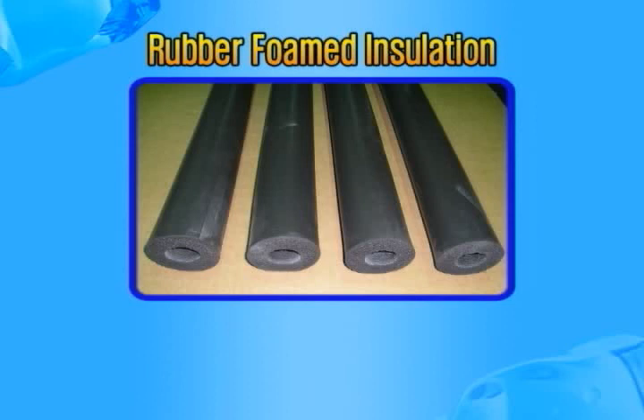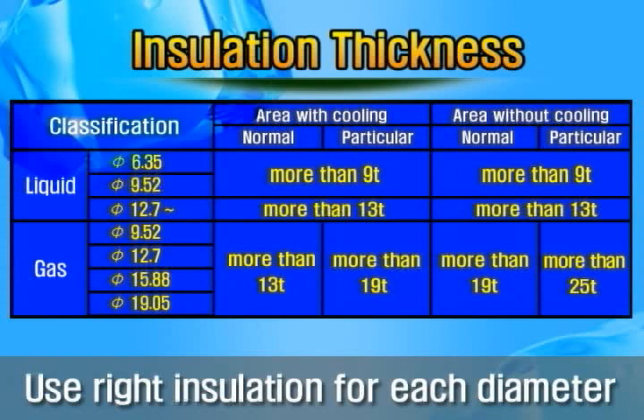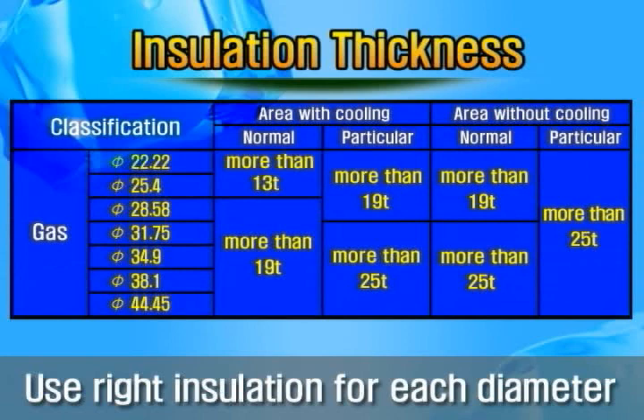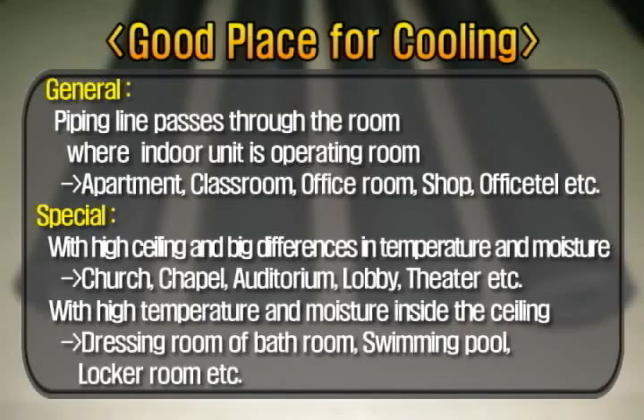Use rubber foamed insulation for refrigerating pipings. Use only the rated insulation, as the dew-forming condition differs with every environment and insulation property. Depending on the cooling performance, the insulation thickness for the liquid line is more than 9 to 13 millimeters, and for the gas line more than 13 to 25 millimeters. As this thickness should vary for every condition, installation should follow the standard manual.